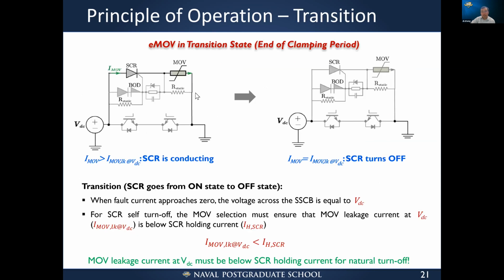And after the current is reduced to almost zero, the VDC will be applied only to the MOVs, and the MOV will have some leakage current. As long as we pick the right MOVs and make sure the leakage current, once the MOV is blocking VDC, is below the holding current of the thyristors, the thyristors will be turned off naturally.